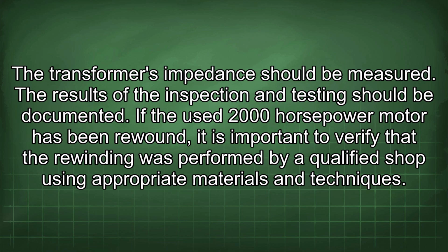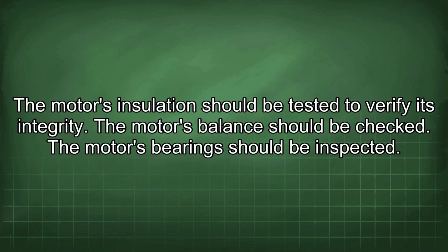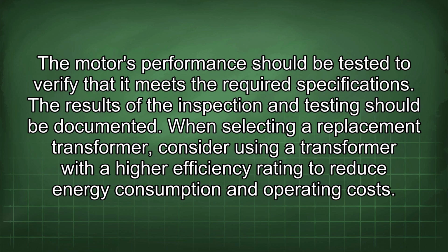If the used 2000 horsepower motor has been rewound, it is important to verify that the rewinding was performed by a qualified shop using appropriate materials and techniques. The motor's insulation should be tested to verify its integrity. The motor's balance should be checked. The motor's bearing should be inspected. The motor's performance should be tested to verify that it meets the required specifications. The result of the inspection and testing should be documented.